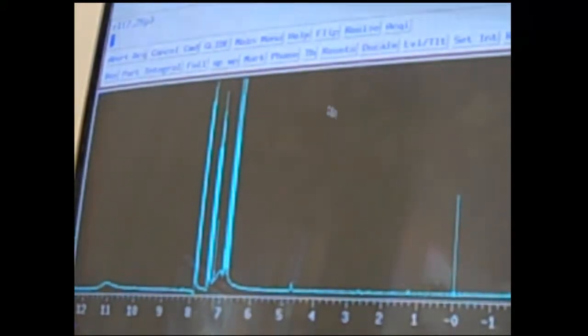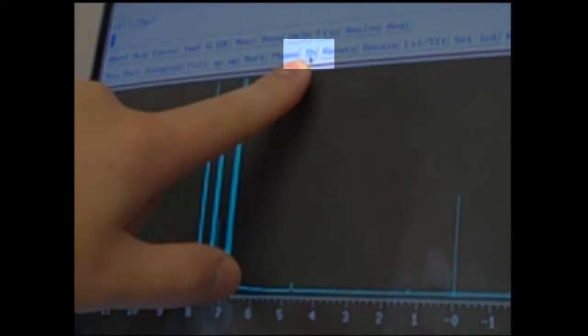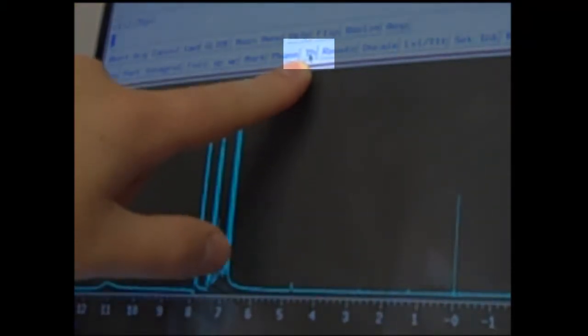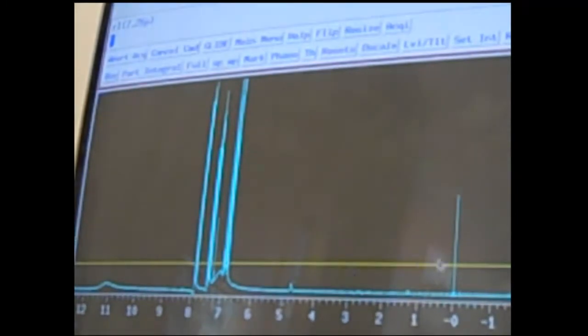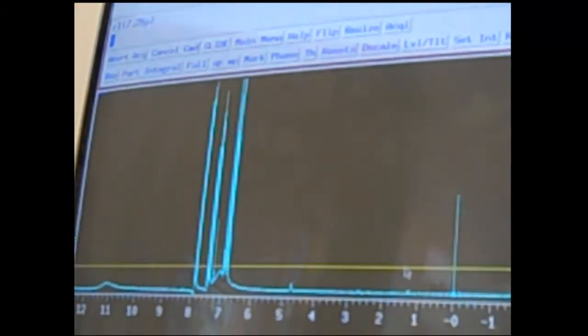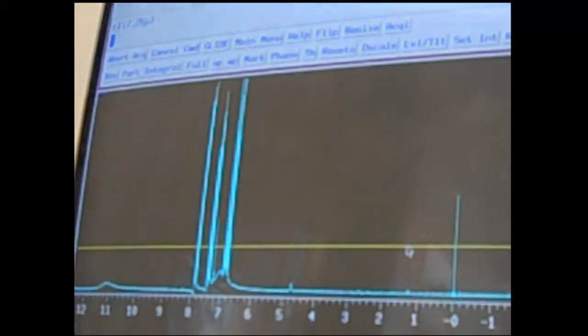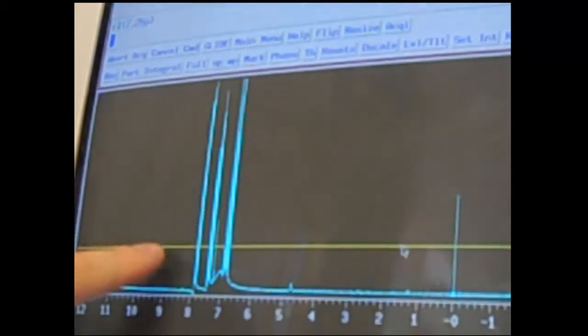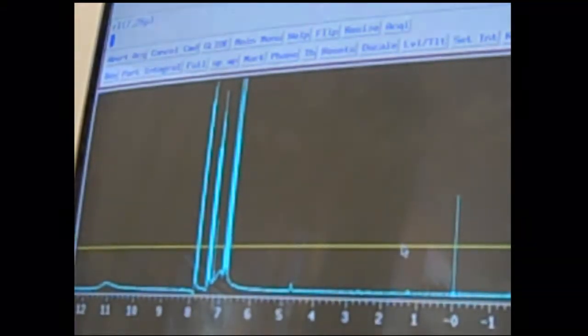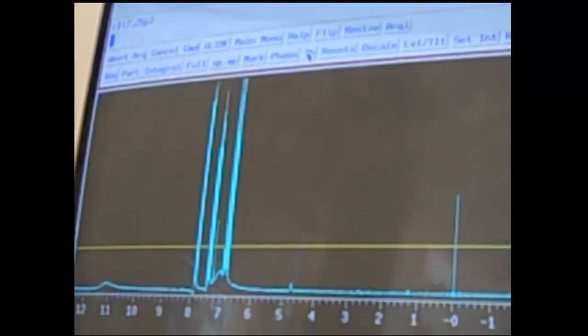At this point you're almost ready to print. One final thing is clicking on this TH button. That's the threshold of peak labels. Clicking it will bring up a yellow line, and then you can left-click to show the height you want that yellow line. That height will then give a peak label for any peak above that yellow line. This seems like a good level, and we can unclick the TH.